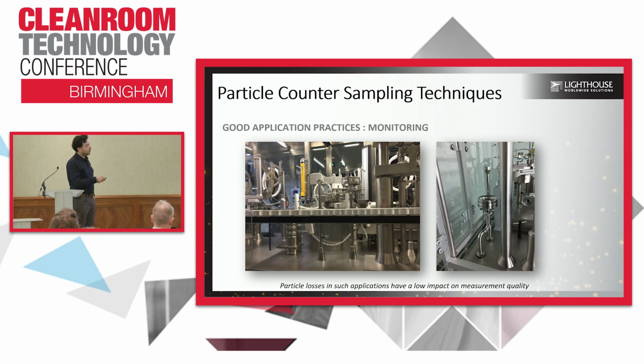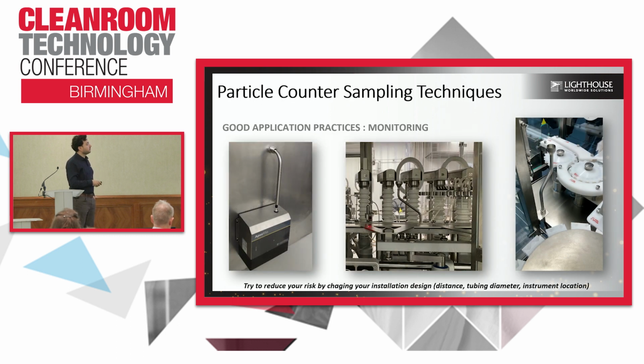Here, we already sampled everything at this point, so the sampling outside of this area is not critical because we're just pulling the air. We're not considering carrying these particles. But if you are sampling through the isokinetic probe, viable or non-viable, you can change this design and evaluate it this way. And the bendings, remember I said this half bending, 45°, we need to move it a little bit to the needle side, so we make a very smooth way so that we are able to pull out. The loss in this tubing compared to the particle counter side by side is less than 3%.